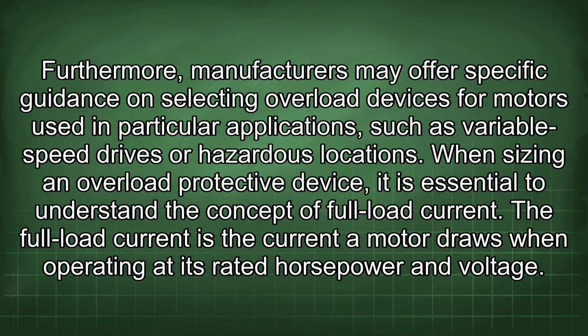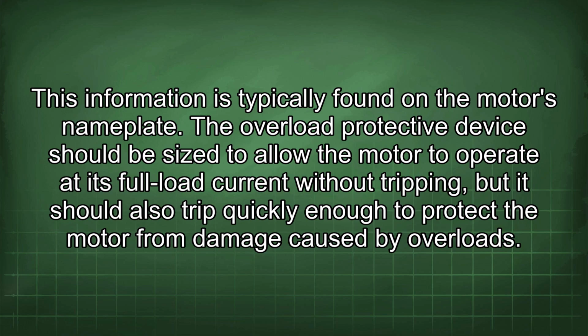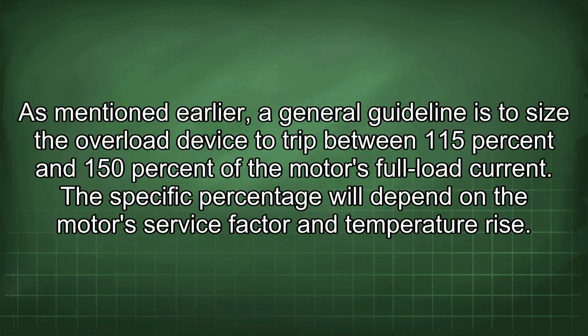When sizing an overload protective device, it is essential to understand the concept of full load current. The full load current is the current a motor draws when operating at its rated horsepower and voltage. This information is typically found on the motor's nameplate. The overload protective device should be sized to allow the motor to operate at its full load current without tripping, but it should also trip quickly enough to protect the motor from damage caused by overloads. As mentioned earlier, a general guideline is to size the overload device to trip between 115% and 150% of the motor's full load current. The specific percentage will depend on the motor's service factor and temperature rise.